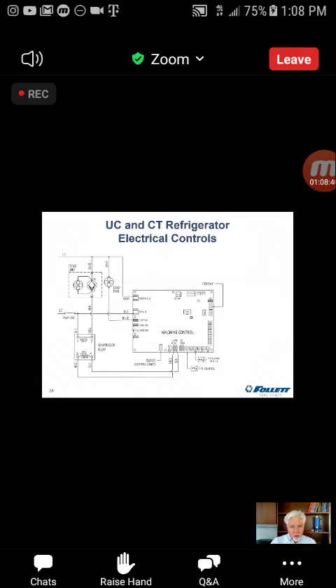So looking at this, when we power up the unit, we've already run through it. Here's our condensing unit. Here's our evaporator fan. As you can see, the evaporator fan is the only thing that comes directly off of the board because of the low power requirement for that. Everything else comes through that outboard relay. It is a solid state relay. So in theory, it should last forever. It has no moving parts, but should it ever fail for whatever reason, you don't have to replace an entire control board. You can leave the brains alone. We're only replacing the muscle, just the relay.